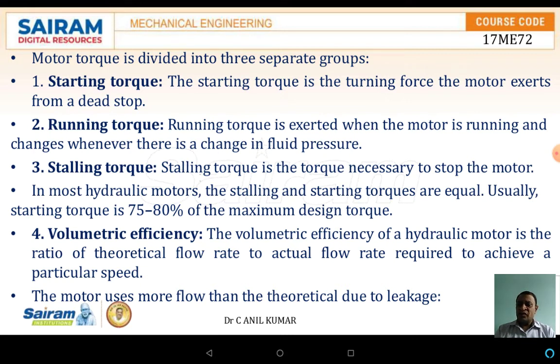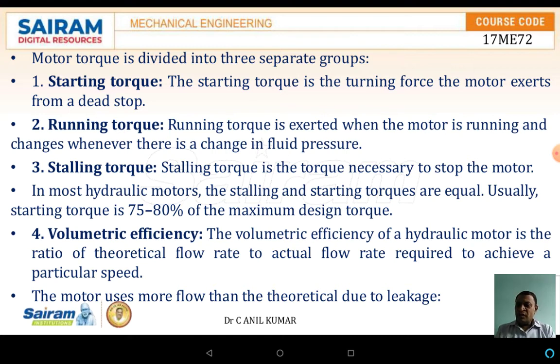Motor torques are divided into three separate groups: starting torque, running torque, and stalling torque. The starting torque is the turning force the motor exerts from a dead stop. The running torque is exerted when the motor is running and changes whenever there is a change in fluid pressure. The stalling torque is the torque necessary to stop the motor. In most hydraulic motors, the stalling torque and the starting torque are equal. Usually, the starting torque is 75 to 80 percent of the maximum design torque.